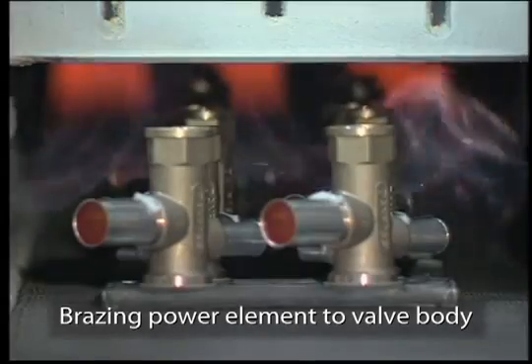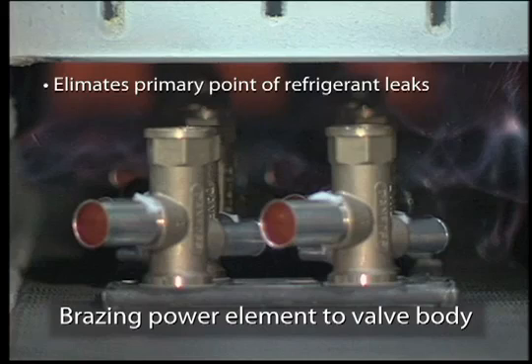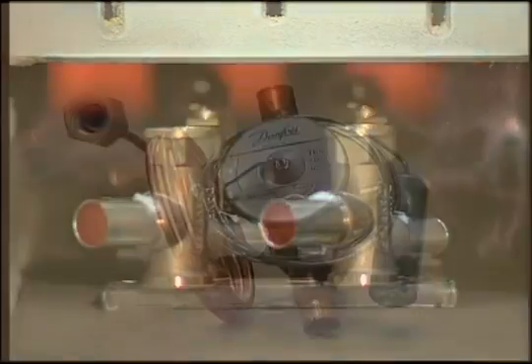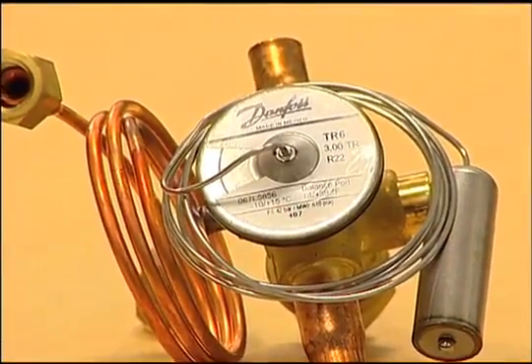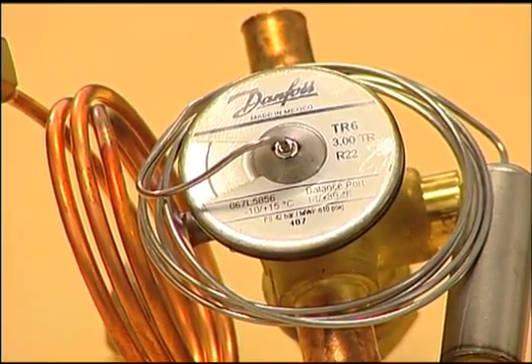By brazing the power element to the valve body, Danfoss has eliminated the primary point of refrigerant leaks in TXVs. A brazed power element also prevents outside debris from coming into contact with the diaphragm — something very likely given the dirty environment in which TXVs are typically installed and serviced. Very small particles of debris have been shown to rapidly wear through the diaphragm, greatly reducing TXV lifespan.